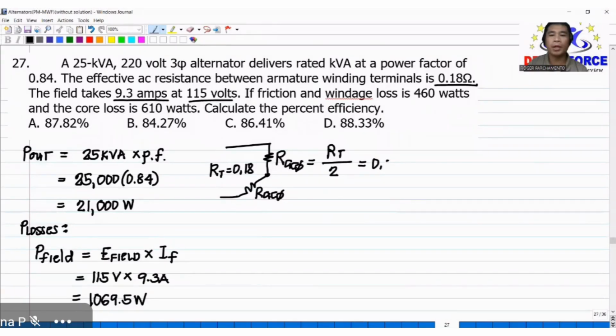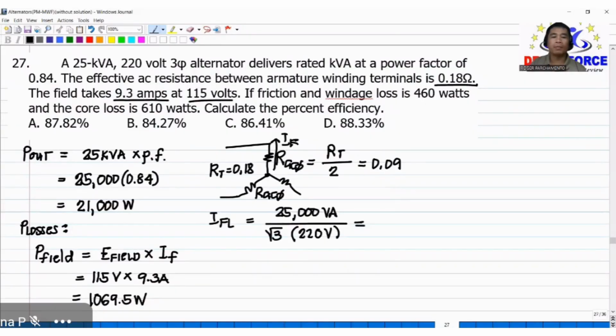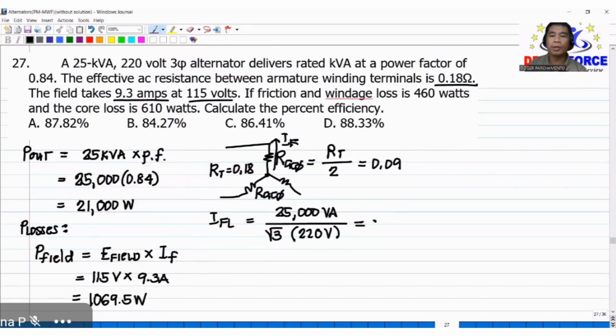So simply 0.09. Tapos may dumadaan na current dyan ay full load. So tatlong fase yan. There are 3 phases. The full load current is equivalent to 25,000 volt ampere divided by square root of 3, so 3 phase yan, times 220 volts. So the value of the full load line current that will be passing through the resistors is 65.608 ampere.